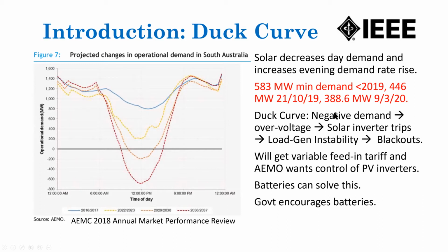At the moment, about half the substation areas where I live have negative flows of power, meaning people are exporting power. When everybody has negative demand, that can lead to over voltage, which can lead to solar inverter trips. If everybody's solar inverter trips at exactly the same time, that can lead to load and generator instability and blackouts. AEMO is getting really worried about this, and they want variable feed-in tariffs and to control PV inverters so they can remotely control people's PV inverters. If they can't do that, they'll have to limit new people joining and putting solar on their roof. Batteries, as I will show, will really solve some of these problems. The government in South Australia encourages batteries, and we actually have a subsidy for installing one.